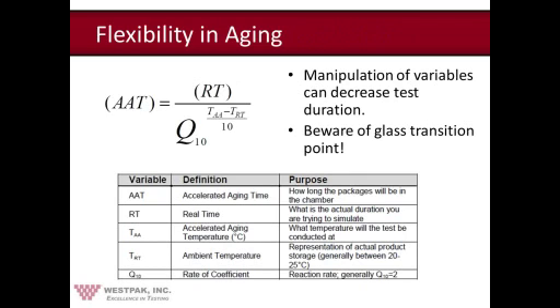As Kevin alluded, accelerated aging testing allows for a package and a product to be subjected to an elevated temperature to simulate the effects of the aging process. Aging temperatures typically range from 45 to 65 C, with 55 C being the most common. And based on the Arrhenius equation, the duration of the test decreases in half for every 10-degree increase in the chamber temperature.